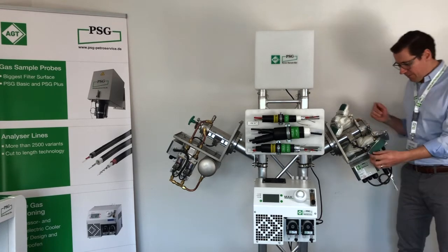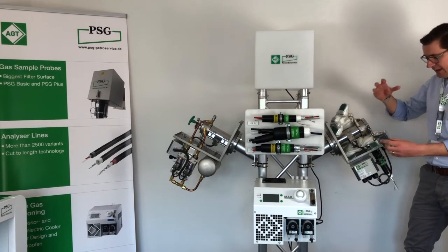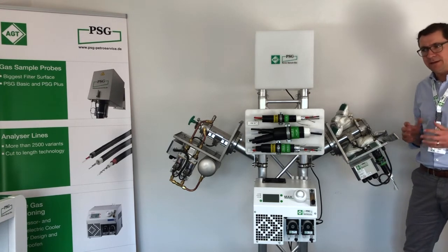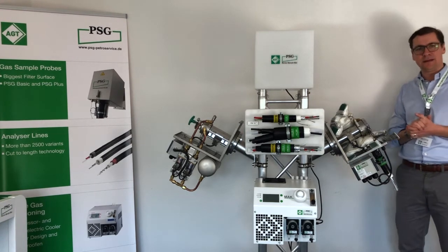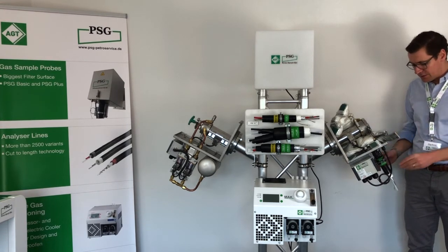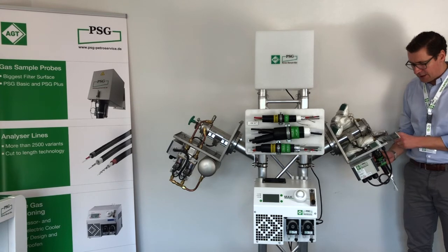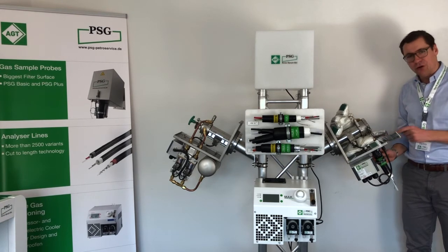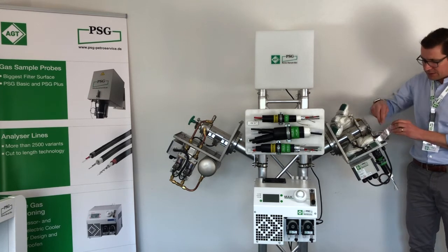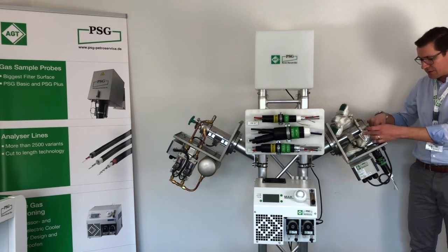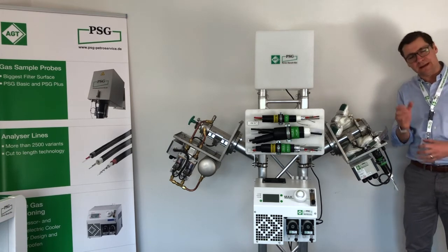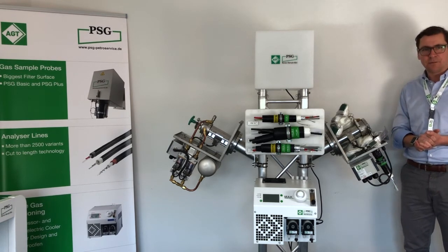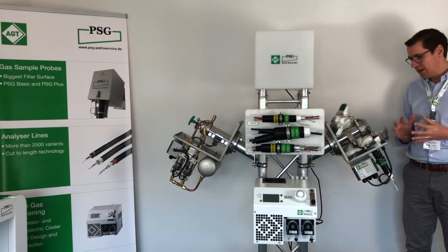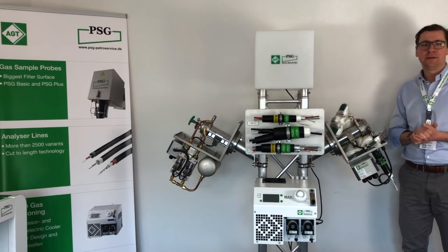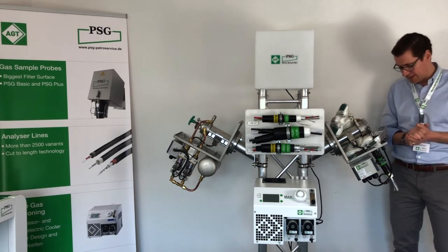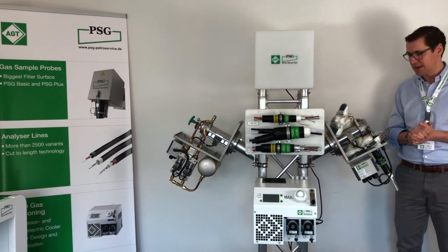Okay, very important, next to the heating of the probe itself, so that it will hold 180, 200 degrees C temperature, is also the connection to the heated sample line. So here we can ensure that there will be no cool spot. You can see that the insulation here is also covering the connection between the heated sample line and the gas sampling probe. So no cold spot will give you dew point problems in this setup, in this very special setup.